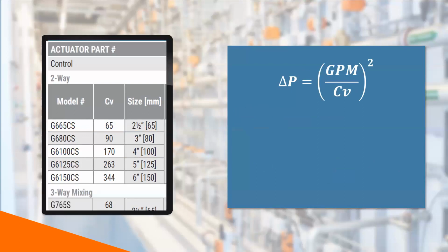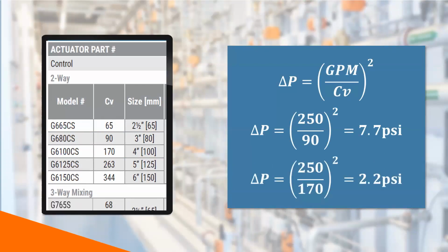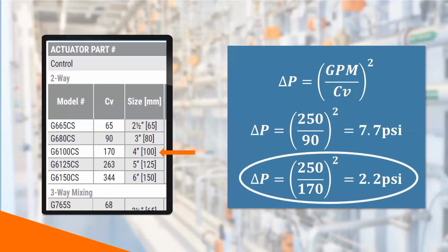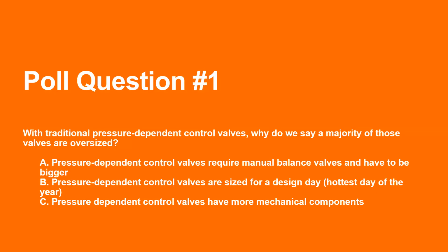Well, to determine that, we would have to solve for the pressure drop and reverse that math. So if we plug in the 90 CV, we get a result of 7.7 PSI, which is over that 4-pound pressure drop that is required. So we solve for the 170, which gives us a 2.2-pound pressure drop. This pressure drop would be acceptable, and we would choose that valve. A valve with 170 CV requires only 2.2 PSI to achieve that 250 GPM. What this means is that our already designed valve that is oversized is even more significantly oversized at this point.